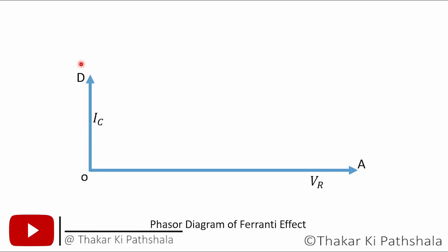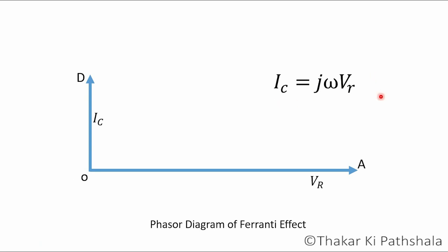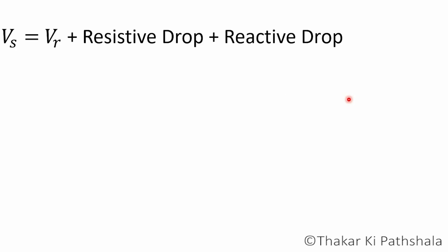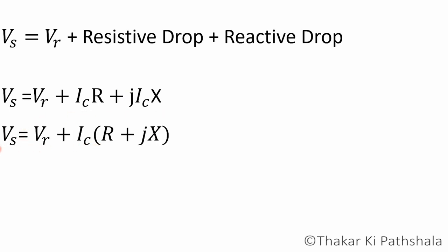Now let's try to understand this theory with the help of a phasor diagram. This is the reference phasor, which is the receiving end voltage Vr, represented by Oa. The phasor for capacitive current Ic is represented by Od, and the value of capacitive current is given by the equation Ic = jωCVr. To draw the phasor for sending end voltage, we calculate: Vs = Vr + IcR + jIcX. Here Ic is common in both terms, so we can write Vs = Vr + Ic(R + jX).